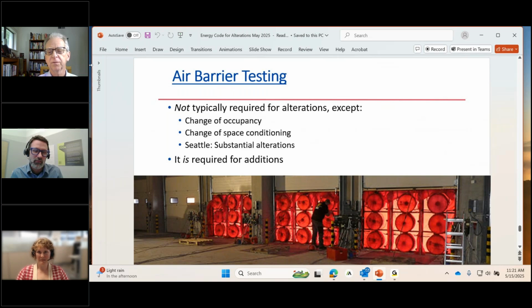If you're not familiar with what was just referenced as a backstop: if you're using energy modeling, since energy modeling was traditionally only used to permit a worse envelope, we've capped that so it can no longer in Seattle be more than 10% worse than the prescriptive code for heat loss, the overall UA, and statewide it's 20% worse.